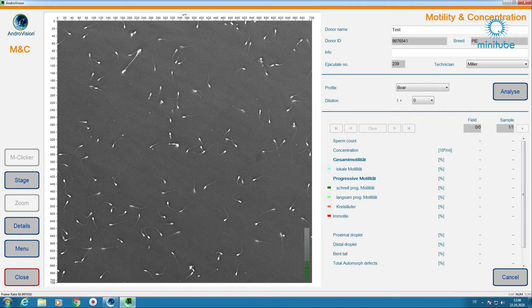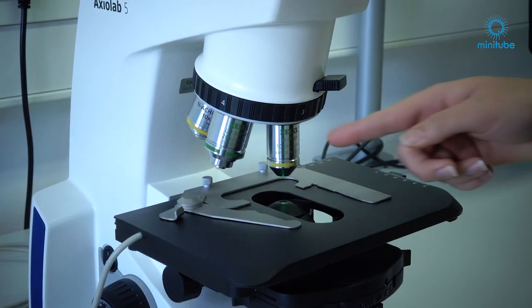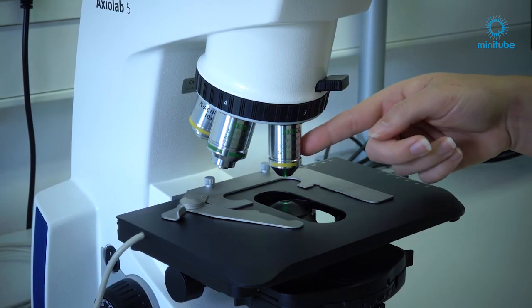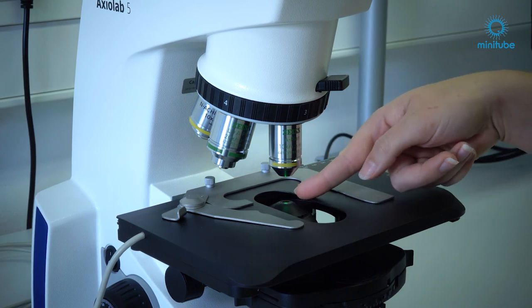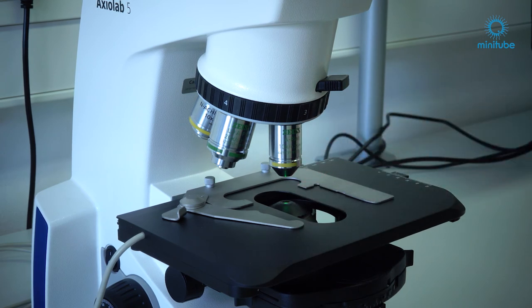What to do when the microscope had been adjusted properly but the picture still appears grayish and unfocused? Please clean the objective lens as well as the condenser lens. Especially extender residues can affect the picture.